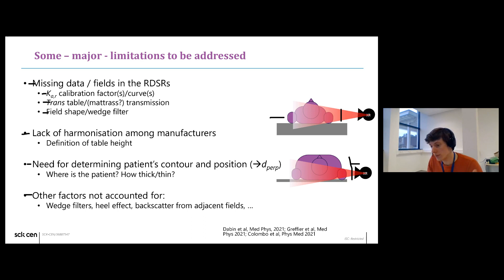Also, there is no real way for the system to know if the patient is rather thin or rather thick. There is information on height and weight, but that's not sufficient, and that again has a big effect on the calculation of the skin dose. And there are other factors that are not accounted for, like the heel effect, backscatter from adjacent fields, and so on. And just to give you an example, we collected data in RDSRs from 160 procedures in 3 hospitals, and we fed them into 4 different skin dose mapping software. You have the list here.